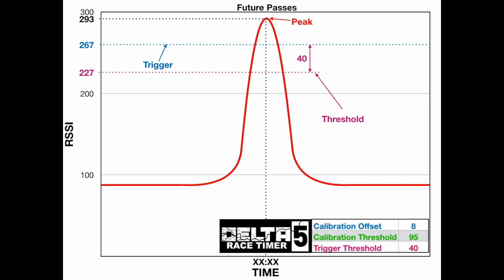So what does that mean for tuning? For the calibration offset, if you were to increase it, obviously your trigger value would be lower and it will make your system a little more sensitive to the RSSI. Same thing goes for adjusting the calibration threshold or the trigger threshold. If you lower those numbers, the amount that the RSSI has to fall on the backside becomes much less and makes the system a little more sensitive.